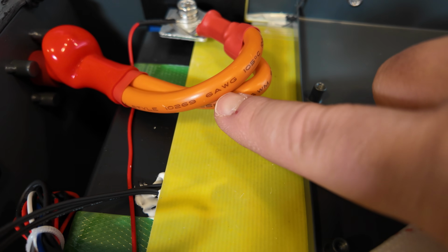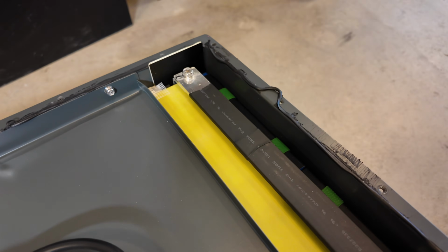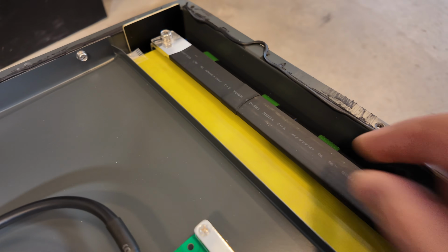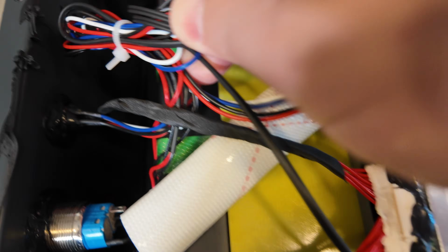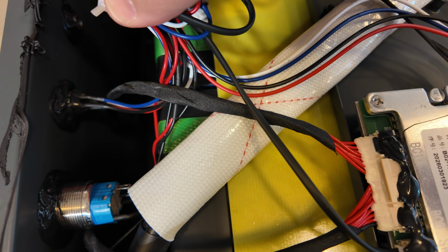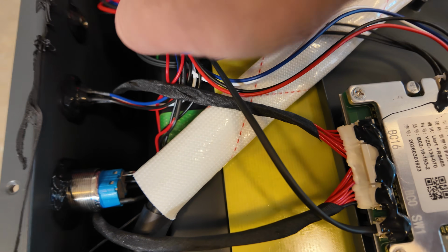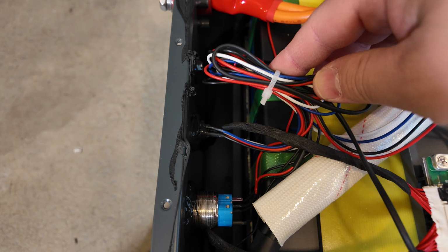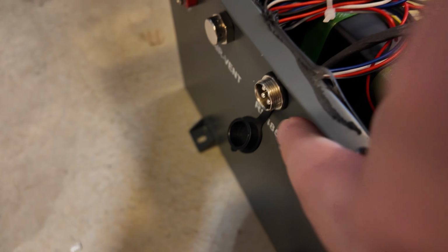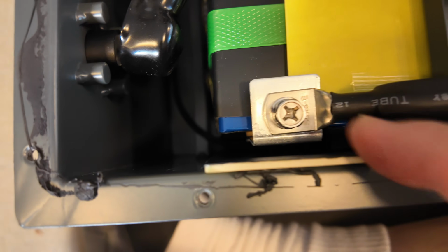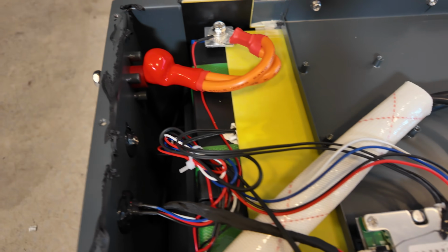On the positive side, we've got two 6-gauge conductors, with physical bus bars connecting to the battery pack. You can see where it jumps from pack to pack, there's a nice thick jumper bus bar. They did some cable management here with a zip tie to bundle the excess wires. Most of these are communication wires that connect up to the screen, while the actual balance leads are wrapped nicely and run down to their respective sides of the battery pack for proper balancing.